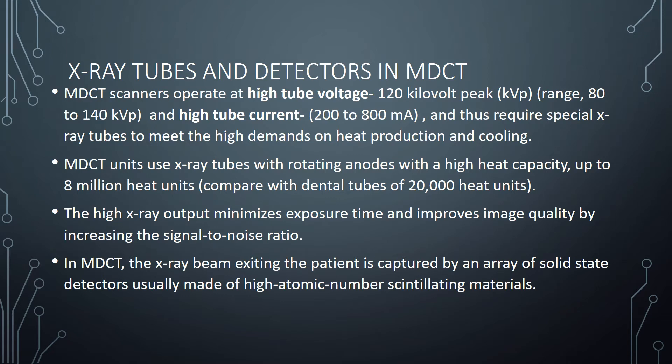When talking about X-ray tubes and detectors in multi-detector CT scanners, these operate at very high tube voltages, generally about 120 kV but ranging between 80 to 140 kV, and have high tube currents in the 200 to 800 mA range. They require special X-ray tubes to meet high demands on heat production and cooling. MDCT uses X-ray tubes with rotating anodes with a high heat capacity of up to 8 million heat units, compared to just around 20,000 heat units for a dental unit.